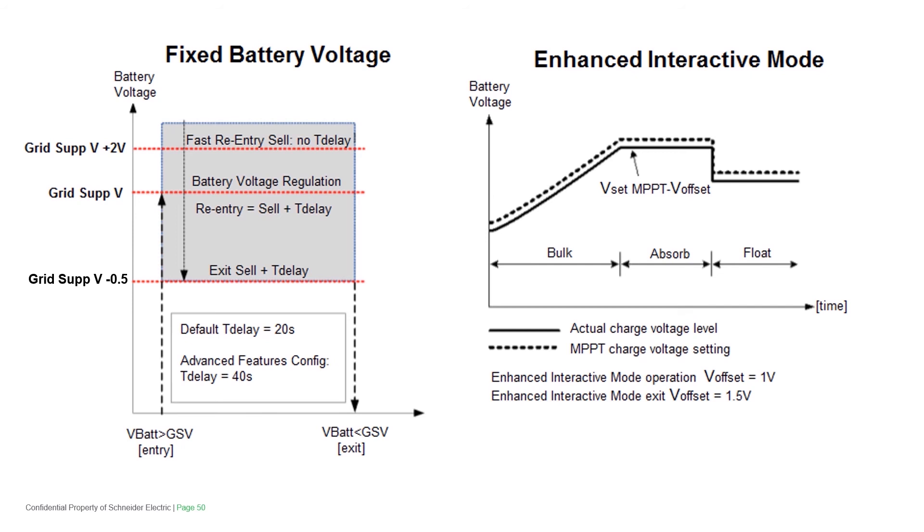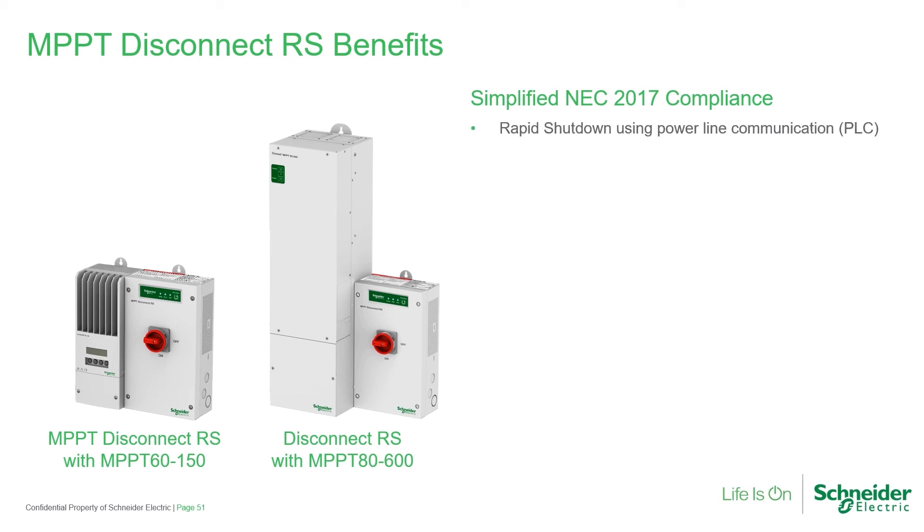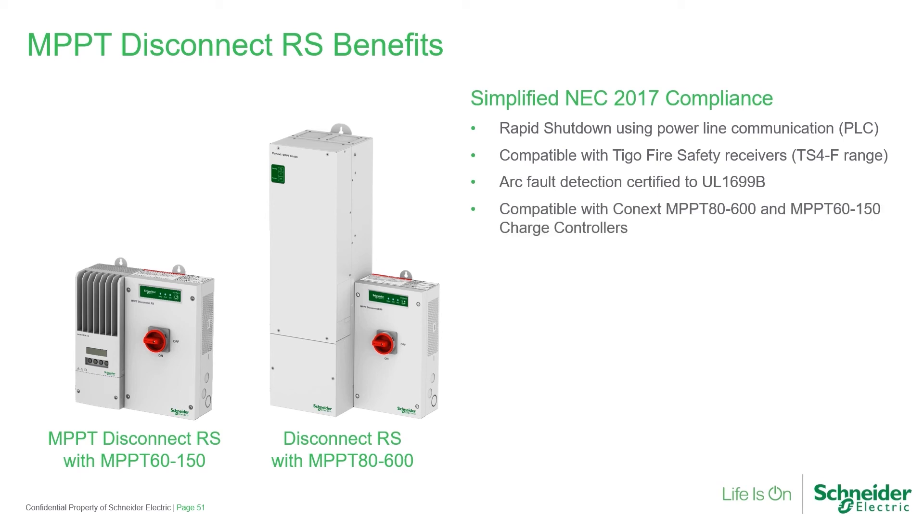Here's a chart that shows how the system operates when setting a fixed grid support voltage as opposed to enhanced grid operation. Once you reach the grid support voltage, if you're setting a standard grid support voltage that's lower than the float voltage of the charge controller, it's just going to start selling the maximum value of max sell amps. Whereas if you're operating in enhanced grid mode, it's going to replace that last 20%, which is actually better for lead-acid chemistry. NEC 690.11 and 690.12 compliance can now be accomplished with our new arc fault rapid shutdown solution, Disconnect RS. Designers now have the ability to keep it all Schneider Electric. This solution uses power line communications, is compatible with Tigo TS4-F, has arc fault detection built in, and is compatible with both the MPPT-80 high voltage controller and the MPPT-60 lower voltage controller.